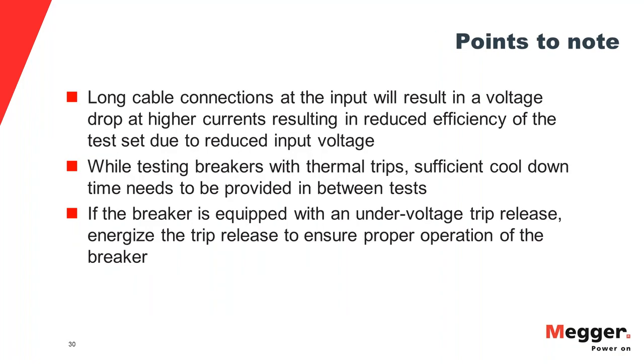So these are the four tests that are done as part of primary injection testing. Some points that you need to make a note of is that if you have really long cable connections at the input, that will result in a voltage drop on the input side if you are drawing a high current. If you're doing the testing at high currents, high output current means high input current for the test set.